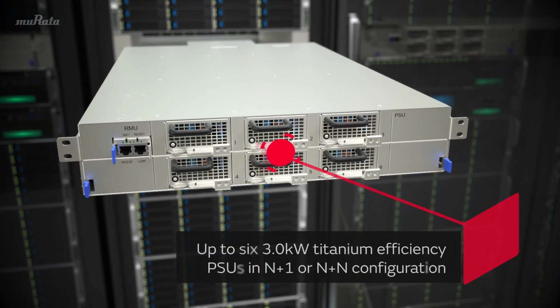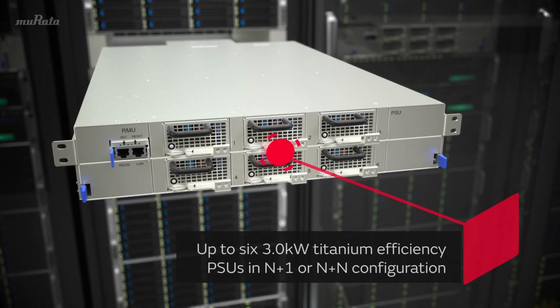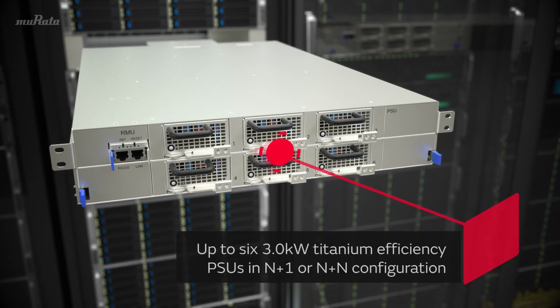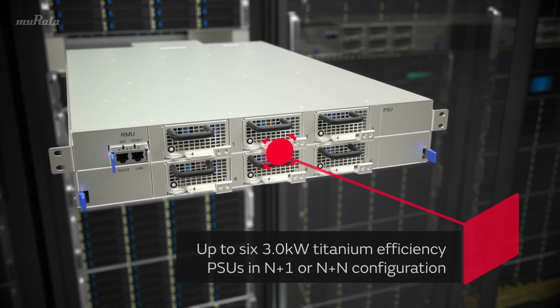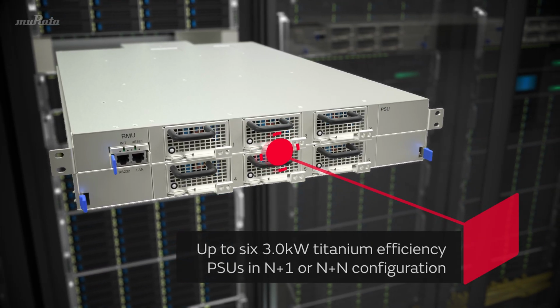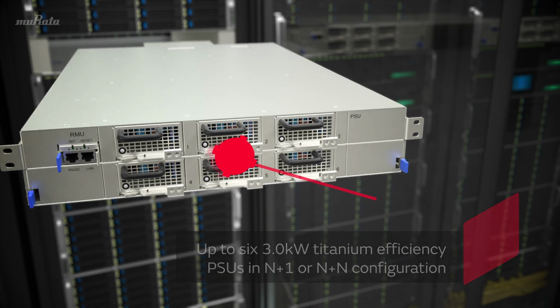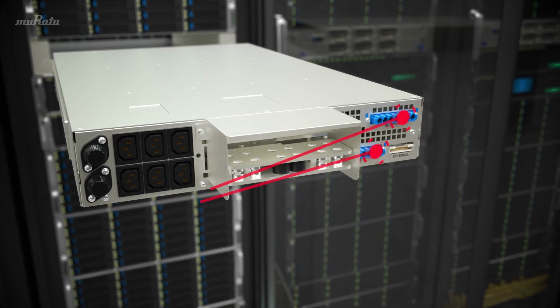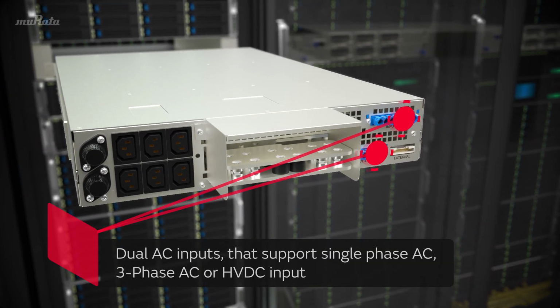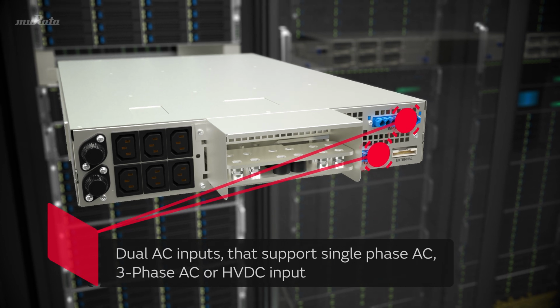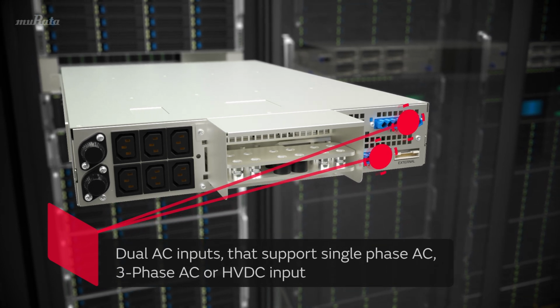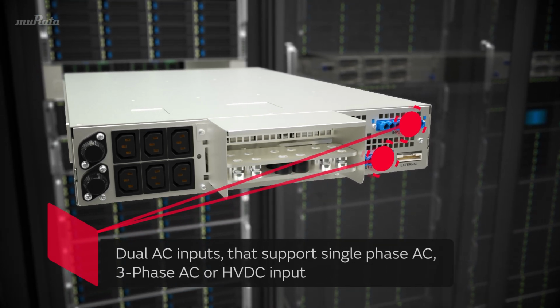Our 12-volt DC power shelf can accommodate up to 6 3-kilowatt power supply units, delivering 15 kilowatts in an N+1 or 9 kilowatts in an N+N configuration. It has dual AC input connectors that support single-phase AC, three-phase AC, or HVDC input configurations for increased flexibility.